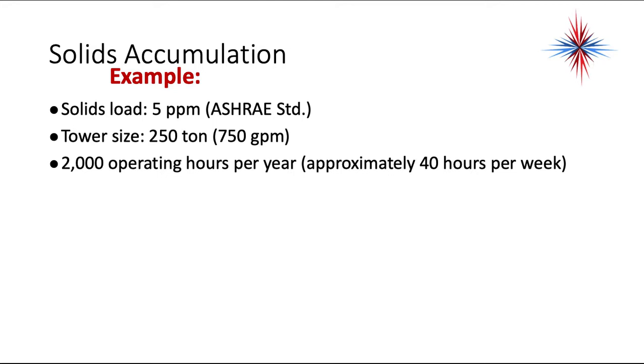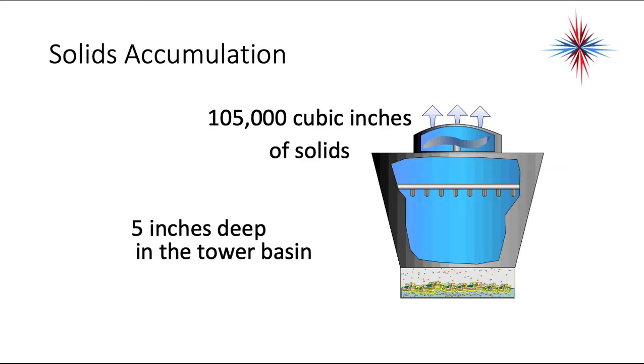There are some guidelines for solids accumulation. For solid load, you can't have over five parts per million — that's the ASHRAE standard. For example, a 250-ton tower with 750 gallons per minute and 2,000 operating hours per year — approximately 40 hours per week — will accumulate 105,000 cubic inches of solids over the year. That's five inches deep in the tower basin.